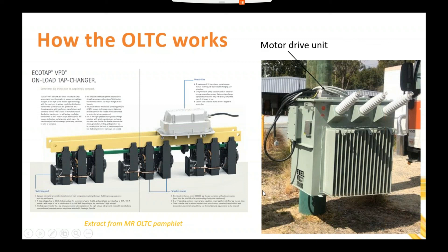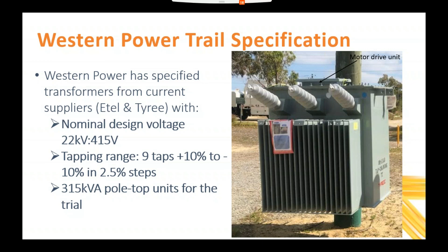So we went for a pretty wide tapping range: 9 taps, plus or minus 10%, 2.5% steps, and we standardized them through 315 kVA pole top units for the trial. The reason we did that is because we had some 100 kVA transformers that needed to be upgraded and some 200 kVAs that needed to be upgraded, and we just jumped straight over the 100 to 200 option and did the one transformer straight to 315, which would make the whole thing a lot more streamlined and cheaper.